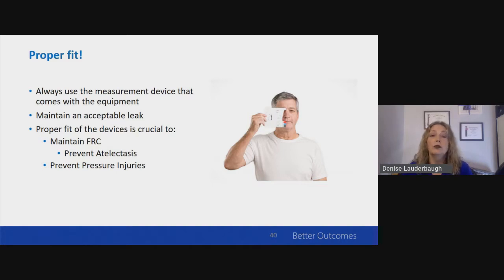When used in conjunction with a ventilator for non-invasive mechanical ventilation or for CPAP, proper fit will allow for an 80% occlusion with pressures 2 to 3 centimeters below what is recommended or written for. And then we set about a 20% leak around the device to make sure that the patient can get rid of their carbon dioxide. If you're using these devices as a high flow nasal cannula, then the manufacturer recommends a 50% occlusion while allowing for a leak. Making sure also that the tubing and connectors don't appear too tight and there's no connections between the bed and the patient.